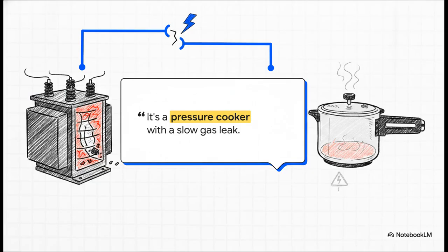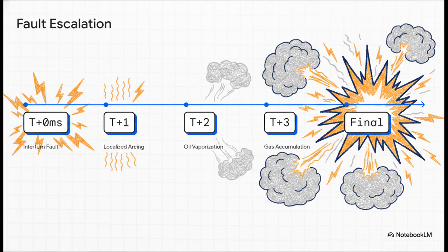Since standard overcurrent protection just straight up misses it, this creates what we call a localized loop trap. I absolutely love this analogy from the source material. It acts exactly like a pressure cooker with a slow gas leak. From the outside, you have no idea. The overall current looks totally normal. But inside, extreme heat and pressure are quietly building up. That intense local heating starts breaking down the winding insulation, and the process just feeds on itself until the whole thing gives way. And if it's left unchecked, this so-called minor fault kicks off a terrifyingly fast escalation timeline.